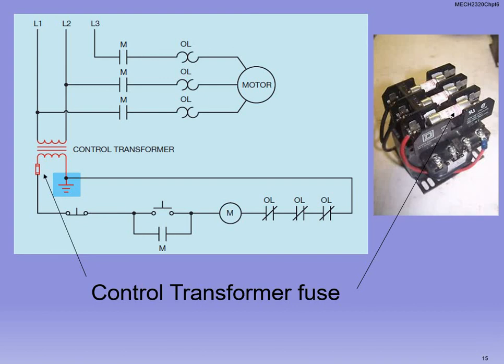Notice the overload relay contactors are all in series with each other, and each one of those overload relay contactors applies to each line that's feeding the motor up above. And then we have the seal-in logic, right? We talk about this in the PLC class. We have our seal-in logic, all right, so that the motor stays in operation until it's stopped, either with shutting off the contactor with the PLC or pushing the stop button. In this case, this is more manual. This is not automatic with anything else. You'll see as we go forward where the controls lie.